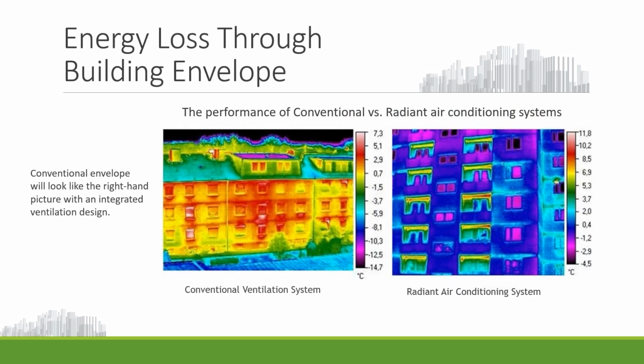If we could look at two different pictures of a conventional ventilation system and a radiant air conditioning system with a thermal imaging camera, we could see that the image on the left is seeping much of the heat that was brought into the building outside through the building envelope. This is very inefficient, and one of the reasons this happens is because the perimeter ducting along the walls, which is necessary to maintain comfort, is also very good at letting that heat that you paid for escape through the building envelope. The graphic on the right shows an integrated ventilation design where hardly any of the heat is escaping, and that's because the thermal energy comfort system of the building is stored in the flooring and the ceilings of the building. It's not being vented anywhere near the building envelope. So the comfort within the building is maintained, and you're also saving quite a bit of money without heating the outdoor environment outside of the building.